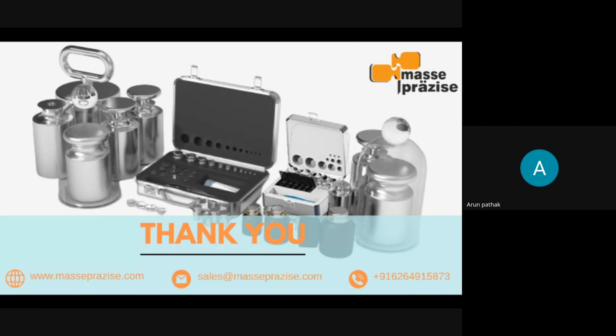To verify standard weight before on-site calibration, do we need to use the ABBA method? We need to use the ABBA method. I think the question is about pre-calibration. Whenever we go out with our standard, we need to perform the pre and post checks. So the ABBA method is common. Whenever you use the weights and you are determining high accuracy, the ABBA method is preferred, and that should be used.